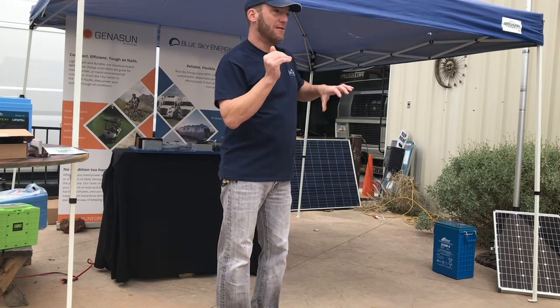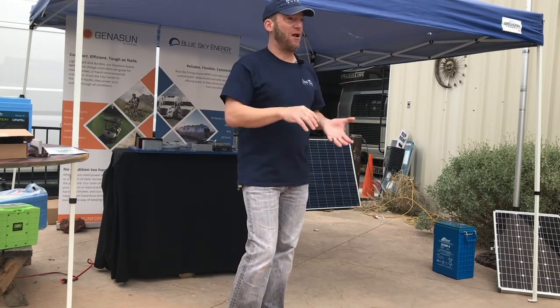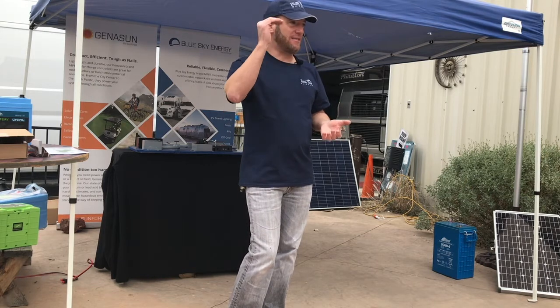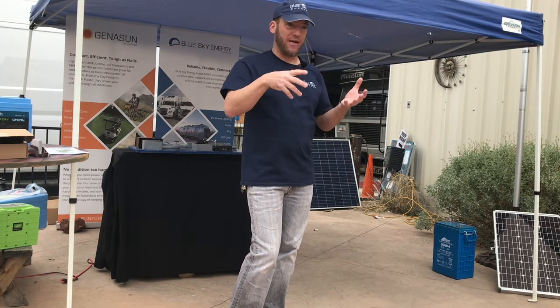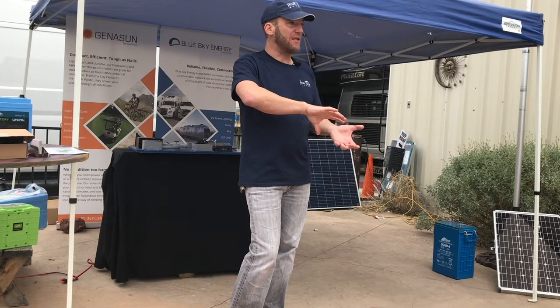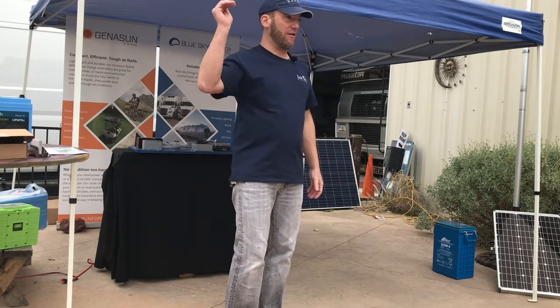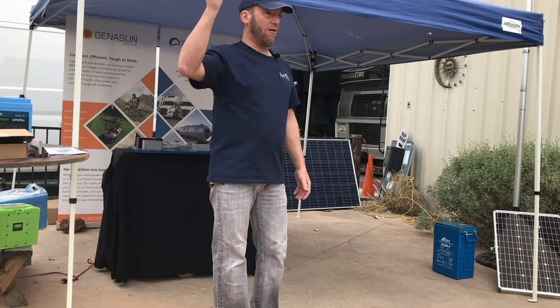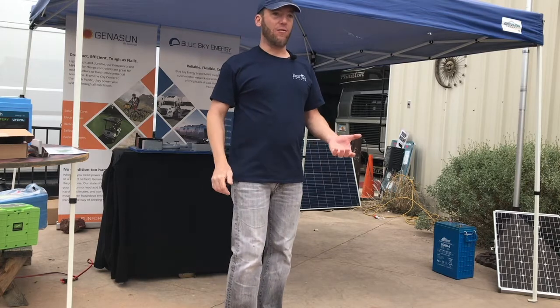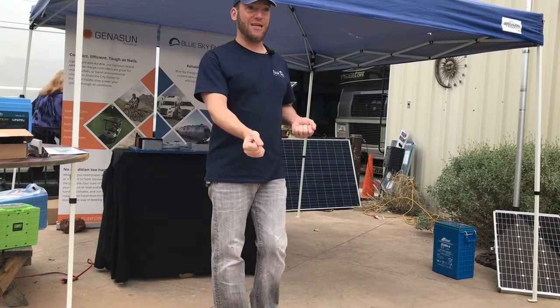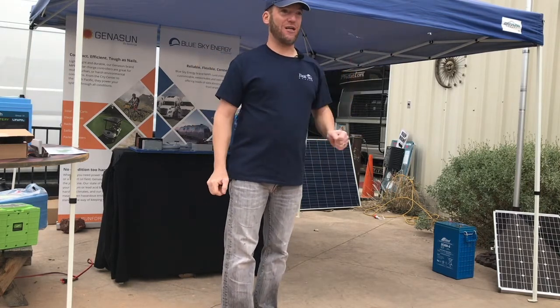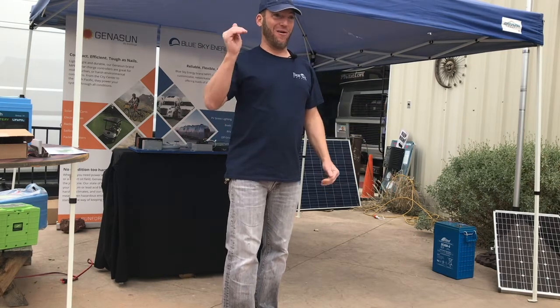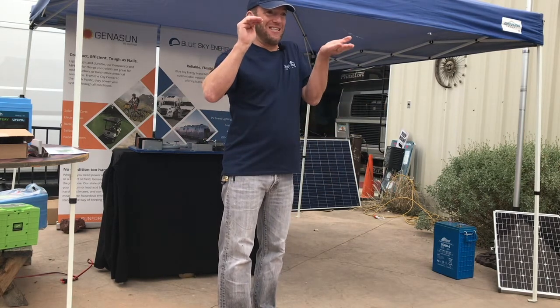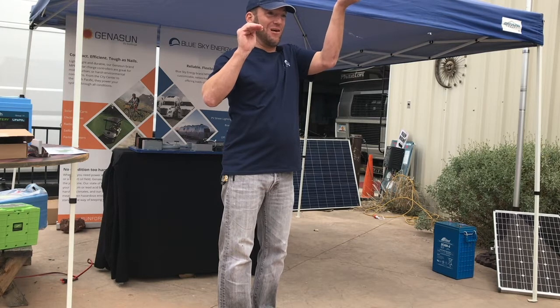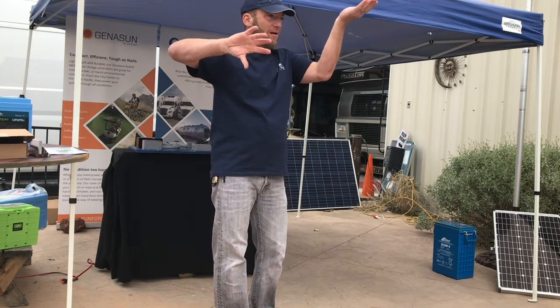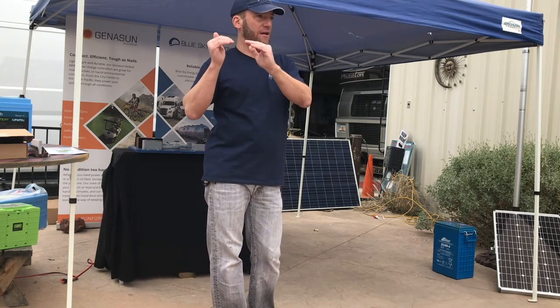So if your actual battery voltage is higher than any set point of your particular controller, its output would drop to zero. Our controller is continually trying to go up to 14.4. Or vice versa—let's say our controller is maintaining a float voltage of 13.2, and you turn on the equalize function of your converter. Our controller will max out its output to get to 13.2, but once your voltage gets above that, our output drops to zero.